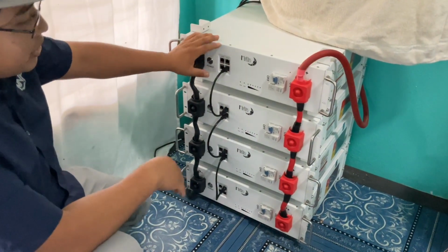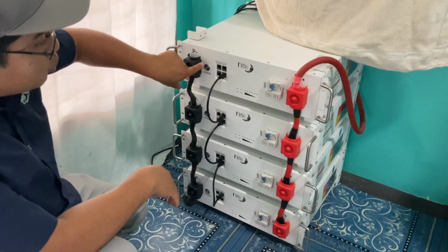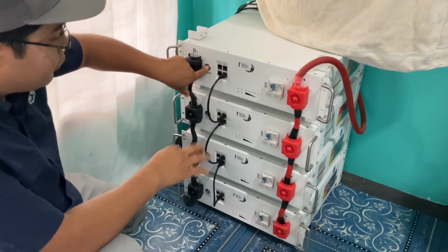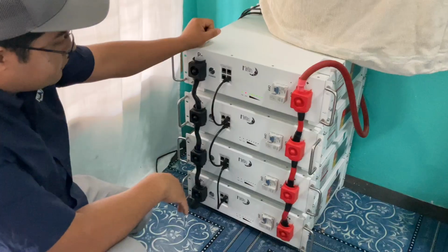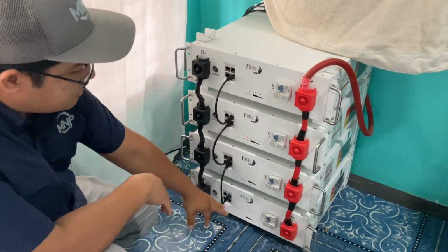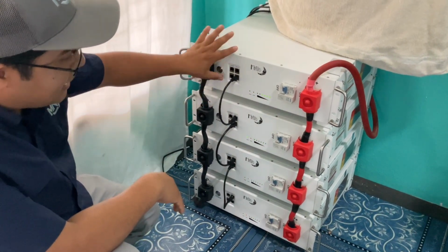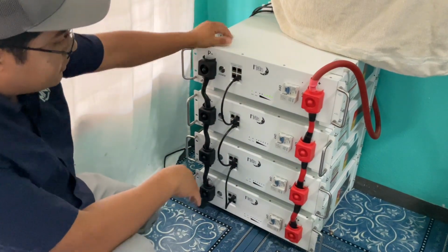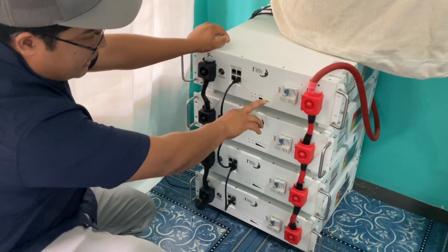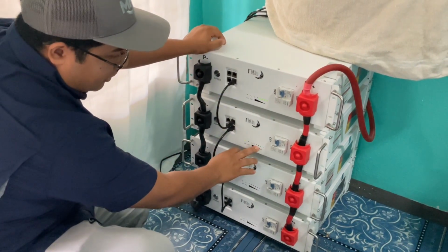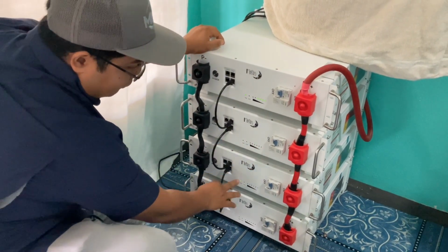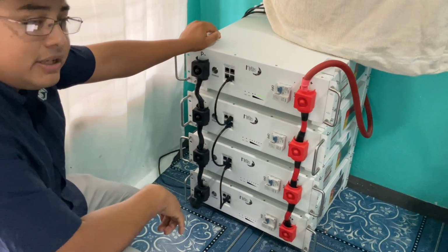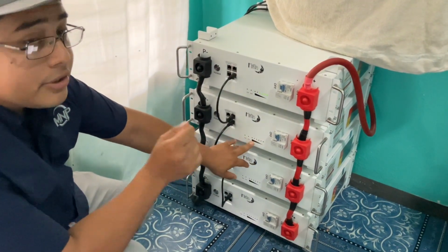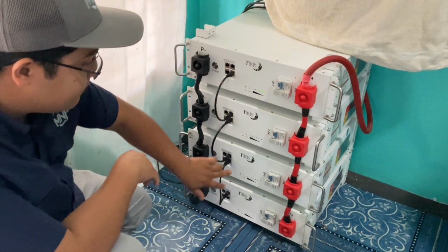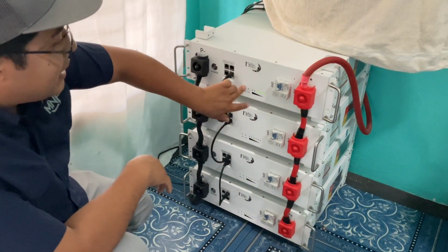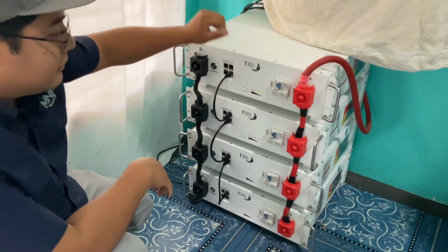Now we're going to turn on these batteries, controlled from the master. Press for 3 seconds. You'll see all the lights start flashing because the master controls all the batteries. The SOC lights will only show on the master battery, and the rest will only have a run light flashing. That's how you know they're all communicating. If any other lights are on, something is wrong. Only the run light should flash on the slaves, while the master battery shows the SOC lights.